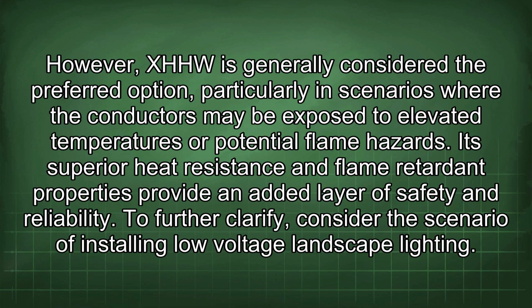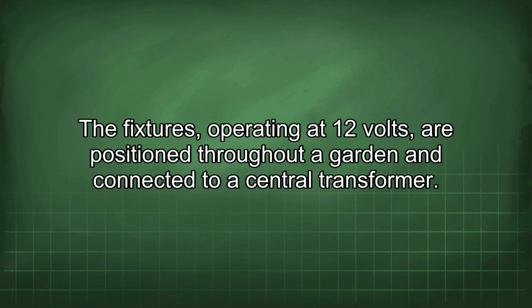However, XHHW is generally considered the preferred option, particularly in scenarios where the conductors may be exposed to elevated temperatures or potential flame hazards. Its superior heat resistance and flame retardant properties provide an added layer of safety and reliability. To further clarify, consider the scenario of installing low voltage landscape lighting. The fixtures, operating at 12 volts, are positioned throughout a garden and connected to a central transformer.